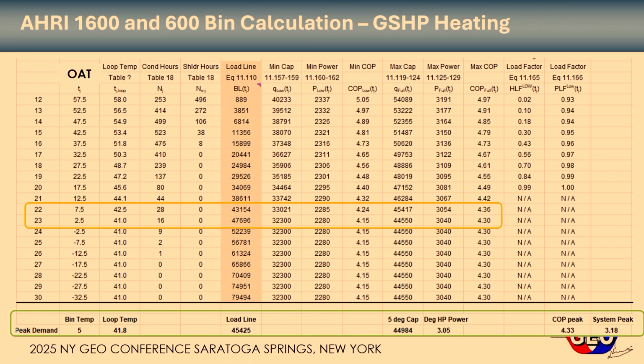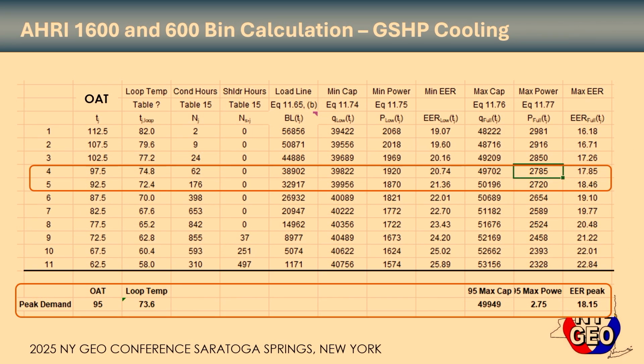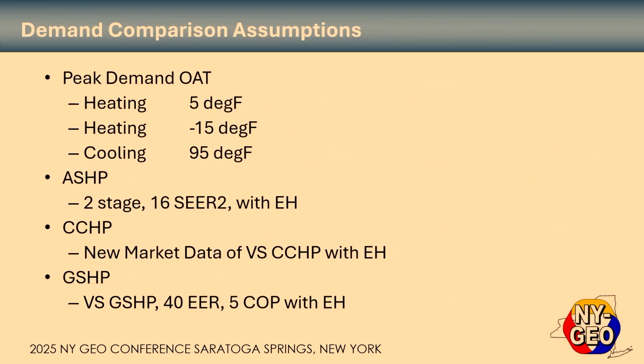And if you look at 5 degrees, the bin will actually tell us how much electric heat we're using, how much current the equipment itself is running. And you can get down at the bottom here, the peak demand at 5 degrees will come right out of the chart. That's where it will be able to be published, and that'll be useful for the utilities, I'm sure, to have certified data at that point. And I won't bore you with the second one.